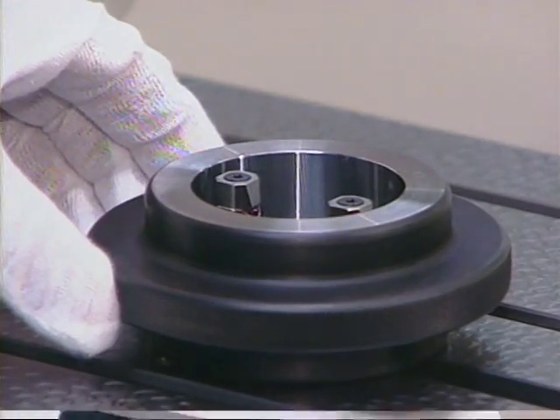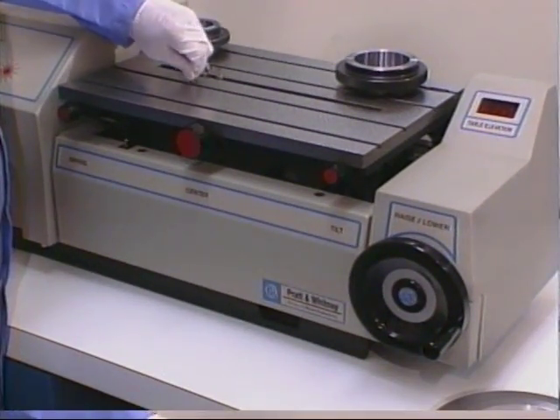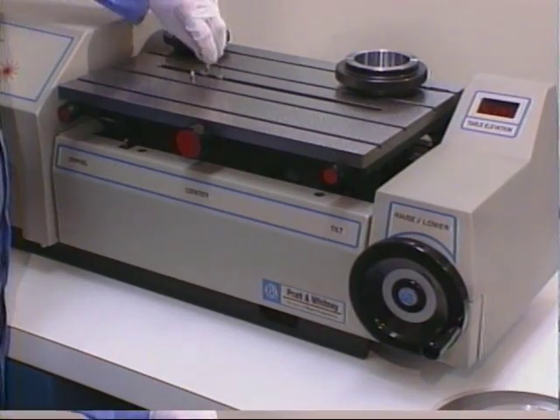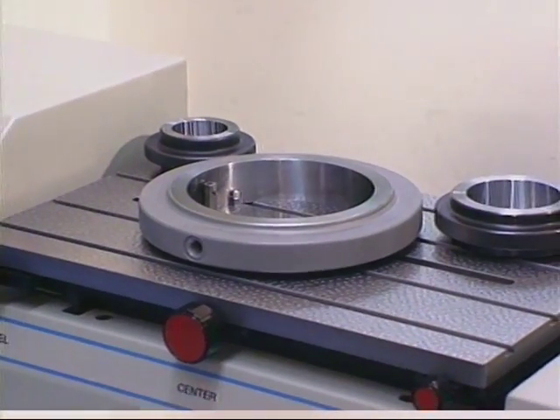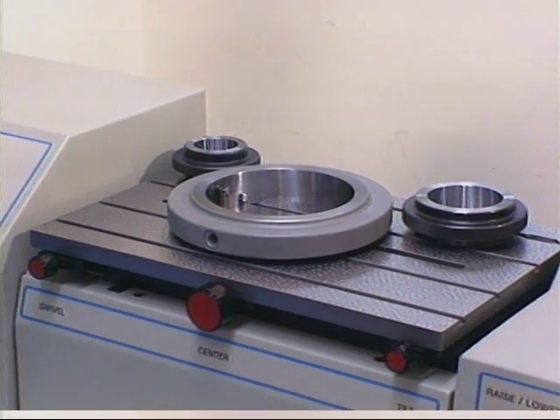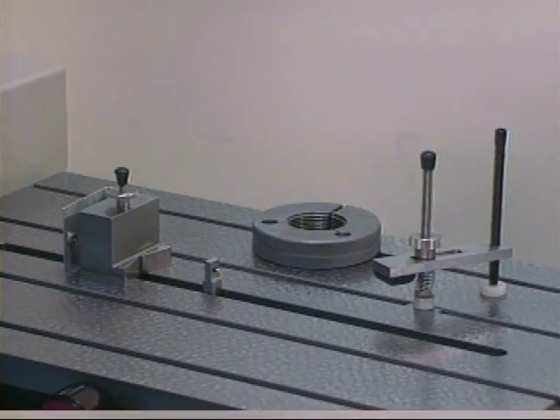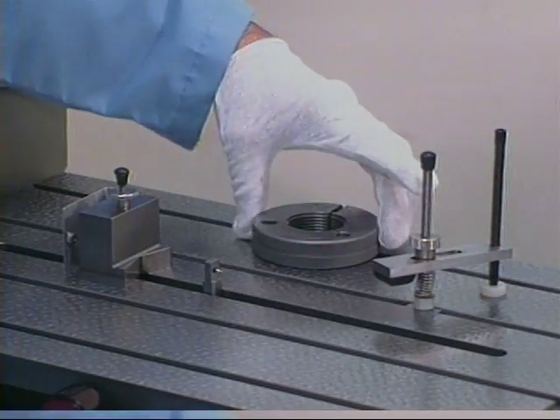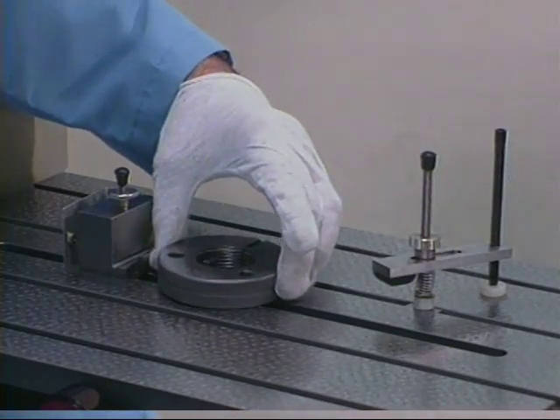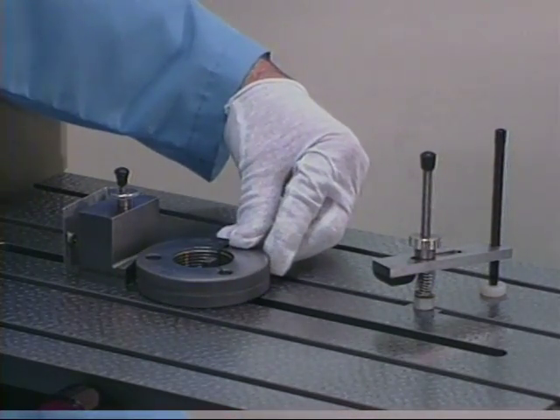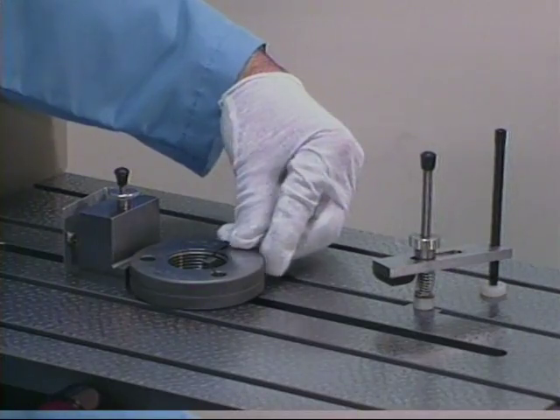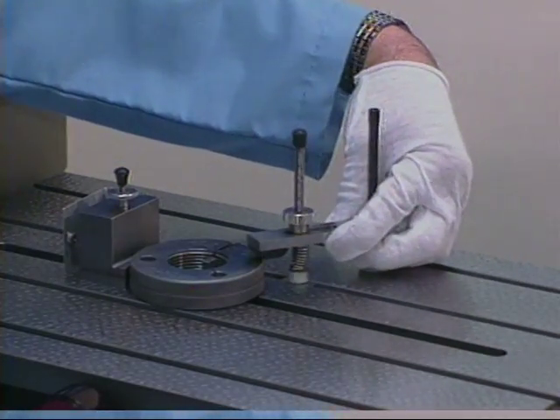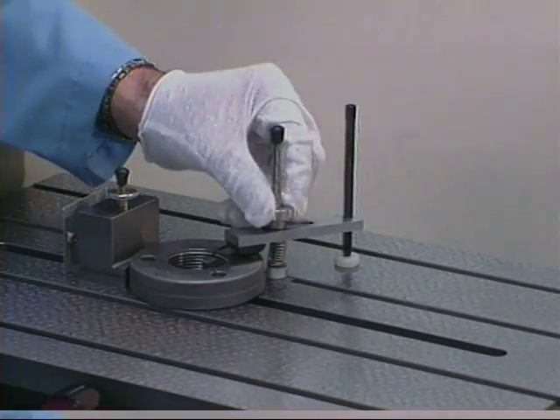By repositioning the locating posts to the outboard position, LabMaster can accommodate larger rings up to 14 inches in diameter. Threaded ring measurement requires a probe reference and internal thread probe for internal pitch diameter measurement. With the accessories set up and a new datum established, we place the ring over the probe. Notice the ring fits in a V to help centralize it.